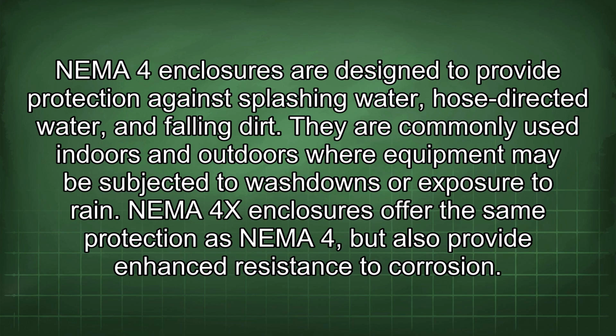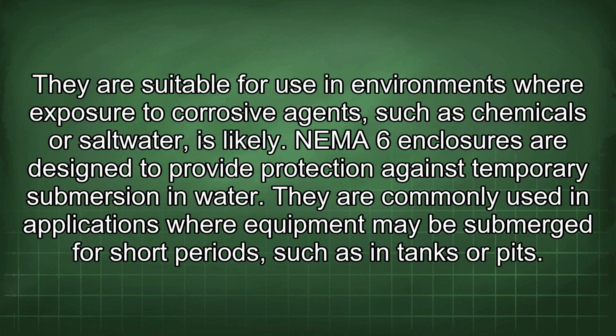NEMA 4 enclosures are designed to provide protection against splashing water, hose-directed water, and falling dirt. They are commonly used indoors and outdoors where equipment may be subjected to washdowns or exposure to rain. NEMA 4X enclosures offer the same protection as NEMA 4, but also provide enhanced resistance to corrosion. They are suitable for use in environments where exposure to corrosive agents, such as chemicals or saltwater, is likely.